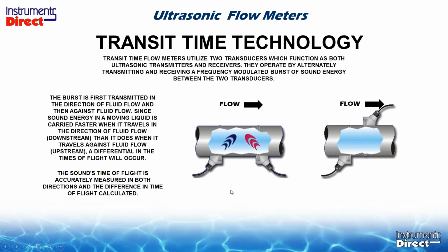So, how does it work? The transit time technology works by clamping transducers on the outside of a pipe. As you can see, we have two different configurations. Basically, the way that this works is the flow going from the left to the right.